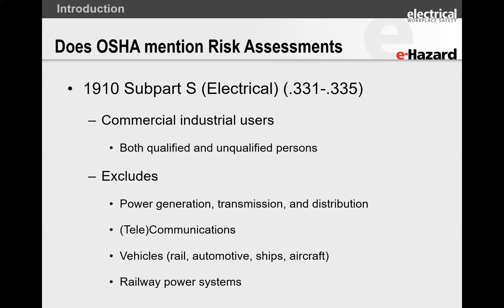The next standard is 1910 subpart S, which is electrical — this applies to commercial and industrial users, and it applies to both qualified and unqualified persons. This covers people who are making food products, packaging, managing high-rise condominiums, and similar operations. What is excluded from subpart S is power generation, transmission, and distribution; communications like telecommunications, 5G, and fiber optic; vehicles including rail, automotive, ships, and aircraft; and railway power systems including overhead lines, distribution systems, and switching stations.